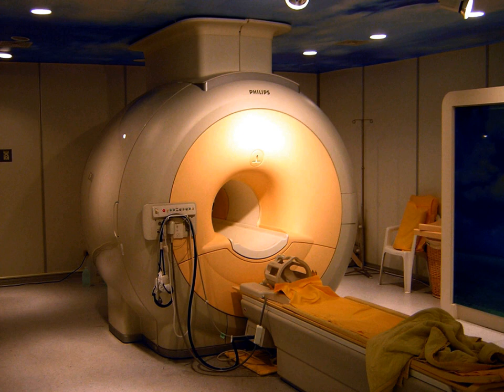Topic: Magnet. The magnet is the largest and most expensive component of the scanner, and the remainder of the scanner is built around it. The strength of the magnet is measured in Teslas, T. Clinical magnets generally have a field strength in the range 0.1 to 3.0 T, with research systems available up to 9.4 T for human use and 21 T for animal systems. In the United States, field strengths up to 4 T have been approved by the FDA for clinical use.